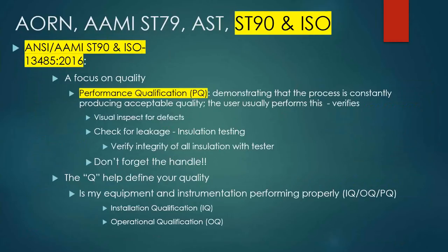So demonstrating that the process is consistently producing acceptable quality - the user usually performs this, which is verifying. A quality measure of the insulation on an insulated instrument is to contain the current, to direct it into one specific place, which is the distal tip, and to use it. So for that instrument to perform properly, somewhere along the line we have to come in and say, okay, I have made sure that no stray current can leak out of any point on this instrument that I don't want it to.